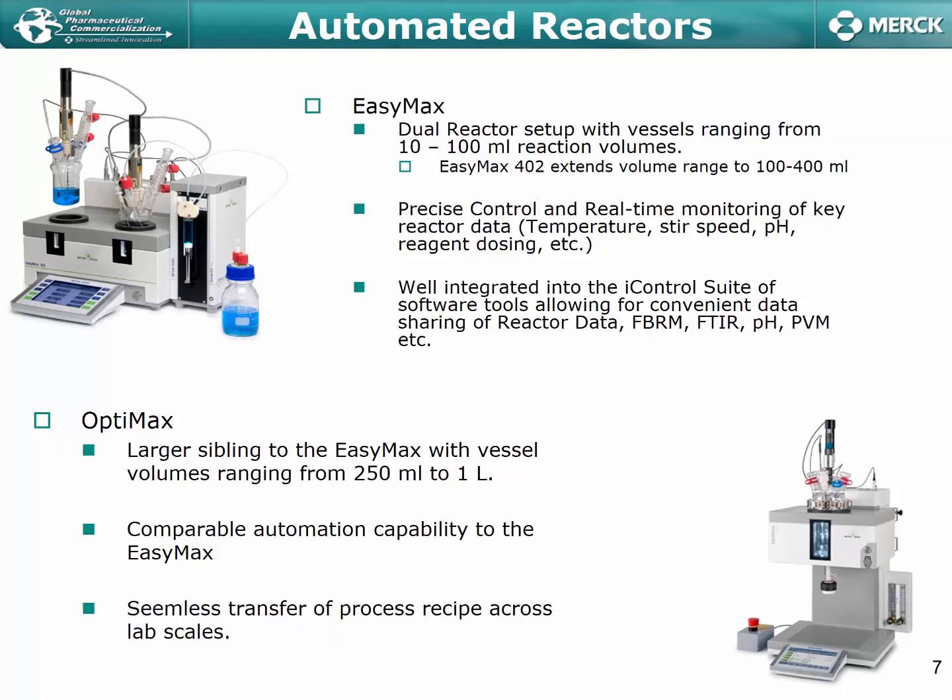Most of the discussion today is a summary of experiments conducted at both the EasyMax and the OptiMax scale. To give a brief overview of the EasyMax: it's a dual-reactor setup with vessels ranging from 10 to 100 milliliters in usable reaction volume. It's an automated system with precise control and real-time monitoring of key reactor data, including temperature, agitation rate, and reagent dosing volumes.